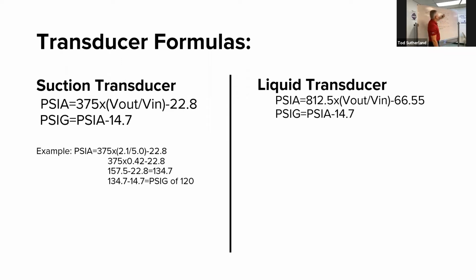Now this voltage out, remember, this is where it gets confusing because I just talked about voltage out from the board. When we're measuring the pressure transducer, we want voltage out from the pressure transducer. So our voltage out is going to be between the black and green wire reading back to the board. So that's going to be your lower voltage. Remember, we said that was our 0.5 to 4.5 volts DC. And then the voltage into the pressure transducer is the 5 volts that we're getting from the board. So we take 375 times 2.1 divided by 5, minus 22.8, which gives us 375 times 0.42 minus 22.8. So it's 157.5 minus 22.8 equals 134.7.